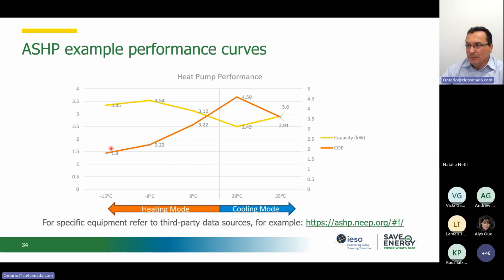So in heating mode, and that's the darker color curve here, the coefficient of performance drops quite fast. So for -16, a temperature that we can see, maybe not many days, but we can still see in heating mode, the coefficient of performance is only 1.8. So that means that we can only take about 2 units of energy from outside, plus the electricity we put in the motor, to deliver in the space. So if the electricity in the motor is the denominator 1, we basically take only 0.8 units of energy from outside. So 1 unit is from the motor, 0.8 from the outside, then we get a coefficient of performance of 1.8 for our heat pump in those really cold conditions.